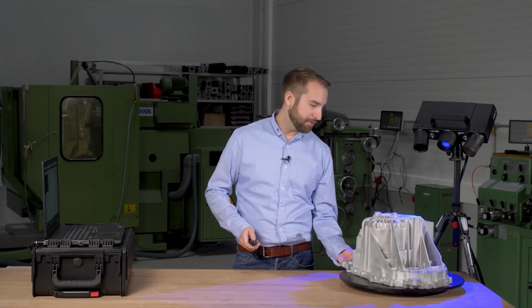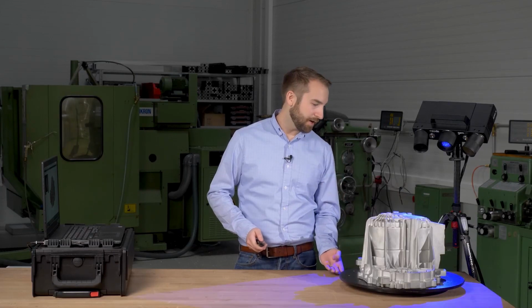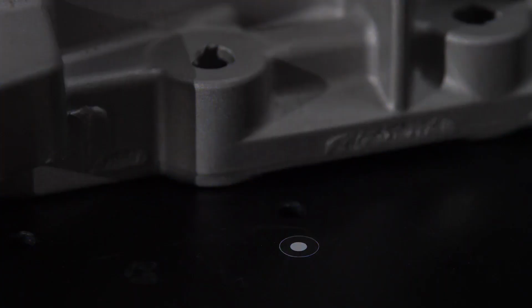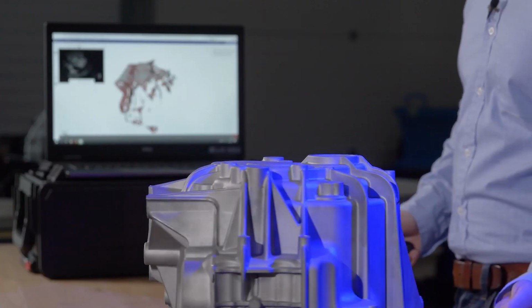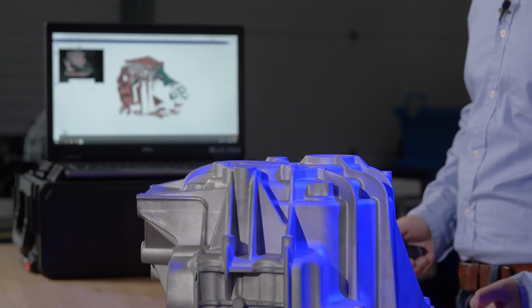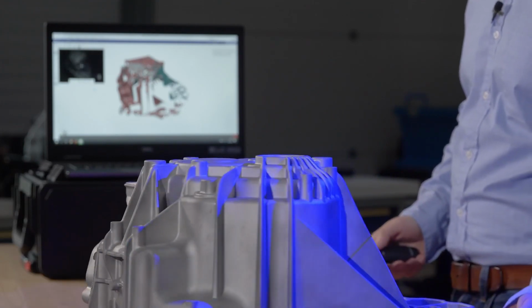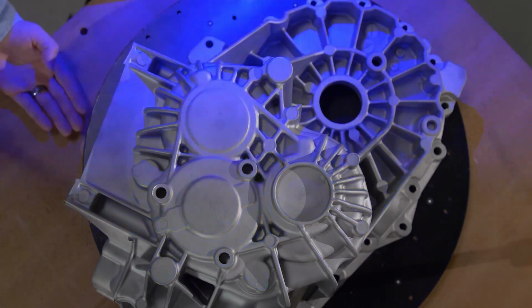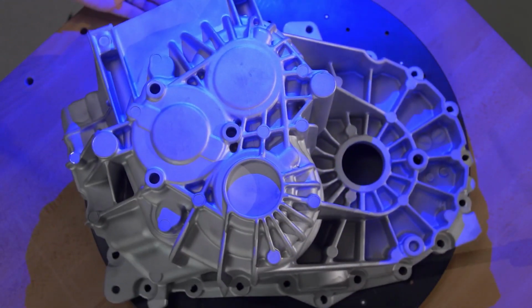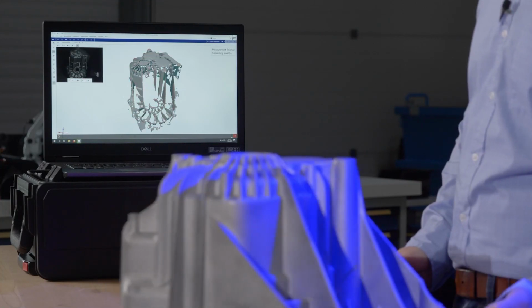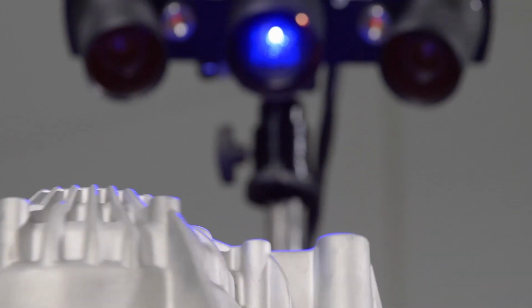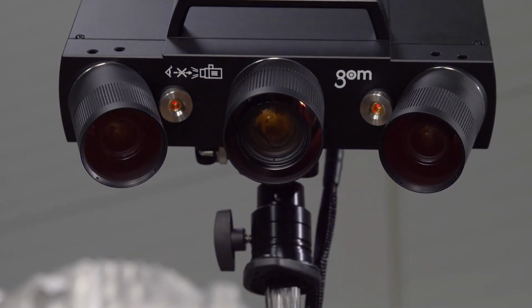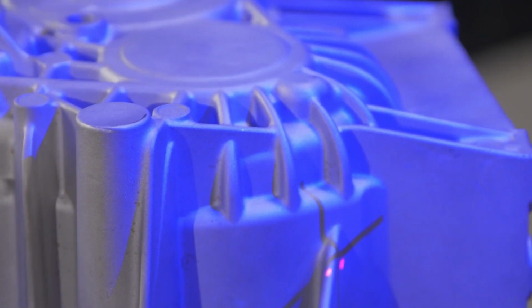For scanning this part, I've put some reference points on the turntable, and that allows us to move the part or the sensor between the scans, and the software can automatically align them together. Also, the ATOS Q is a very fast sensor, and we're capturing up to 12 million data points per scan. The ATOS Q takes advantage of all of the latest GOM technology. This includes the triple scan functionality, which allows us to capture data in even hard-to-reach areas. Additionally, the system uses a fiber optic cable connection, 2 fast cameras, and the latest GOM fringe projection techniques in order to ensure that we have very accurate scan results.